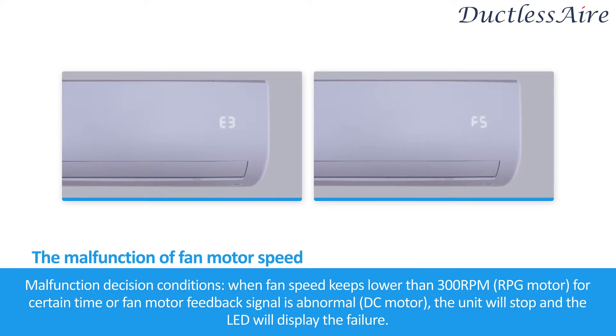Malfunction decision conditions: When fan speed keeps lower than 300 RPM (RPG motor) for a certain time, or the fan motor feedback signal is abnormal, the unit will stop and the LED will display the failure.